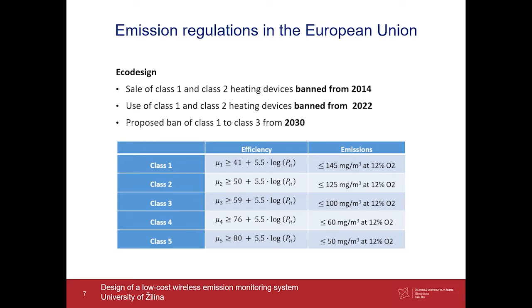To counter this, the new European Union regulation number 2015/1189 endorses the Eco Design Directive. The directive defines minimum mandatory requirements regarding emission and energy efficiency of boilers, and classifies boilers into 5 distinct classes, Class 1 up to Class 5, based on emission and efficiency measurements. From the beginning of 2022, the operation and production of boilers of emission class 1 or 2 shall be legally banned. From 2030, it is considered that all 3 lowest classes will be banned from use. These boilers must be identified and replaced by then.